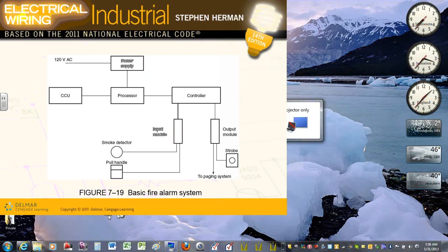And if one of them goes off, it will alarm, and it will tell you which one of them, because they each have a digital address. Every one of them will have a digital address. The same thing for the output, guys. You have strobes, or you can interface with the security system, paging system, lock system, open the doors. You can send the signal, supervised ones. You have to send the signal to the fire department and a bunch of other things.